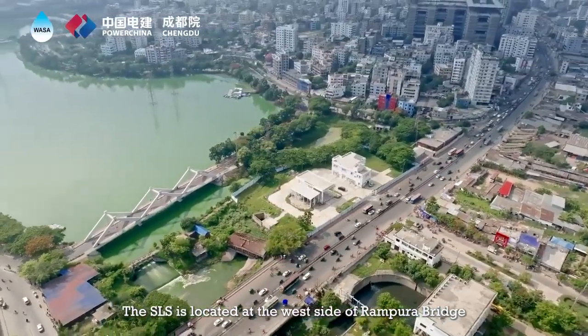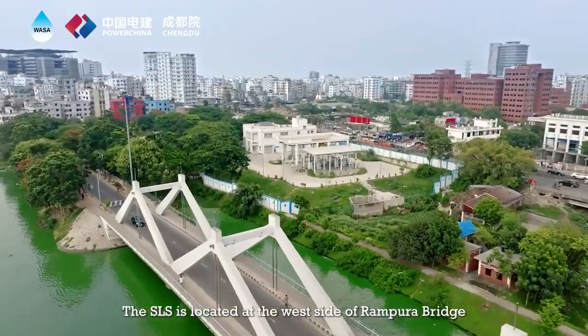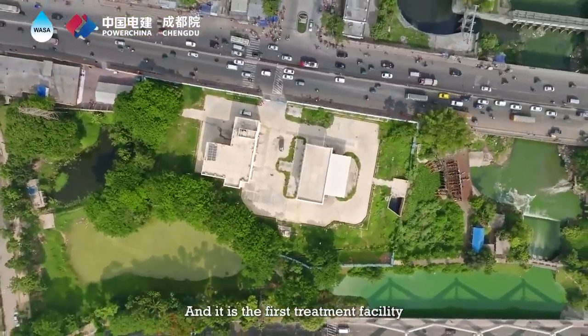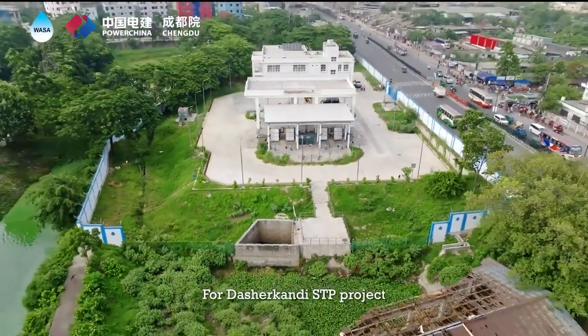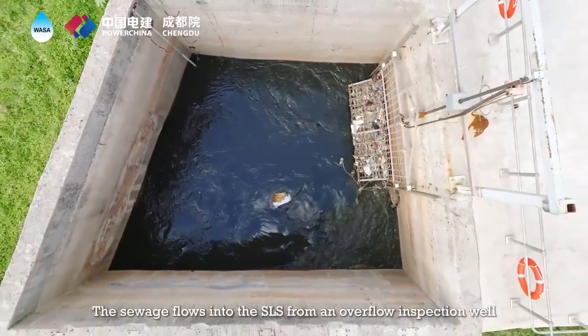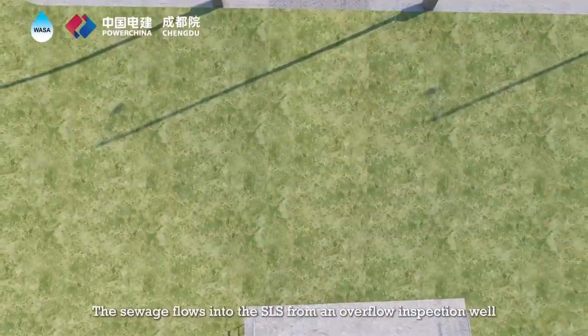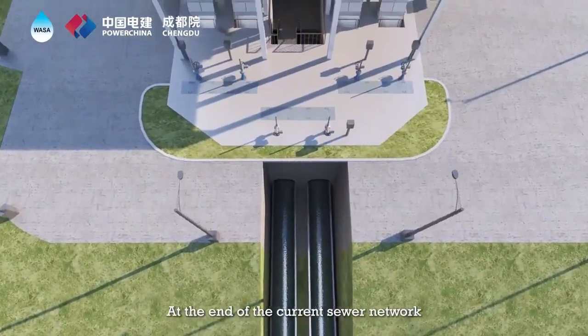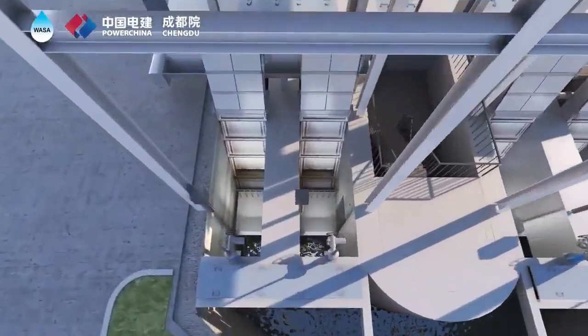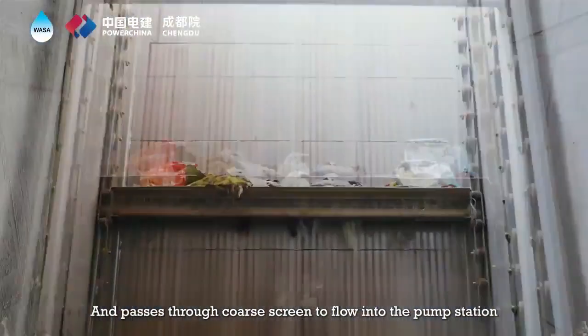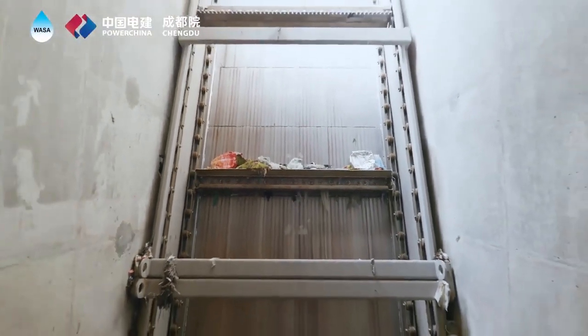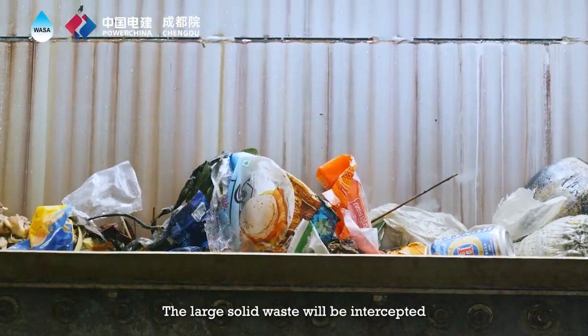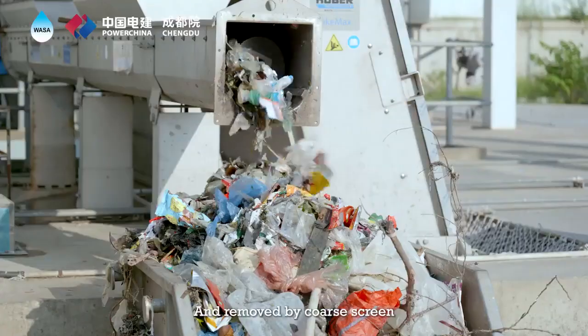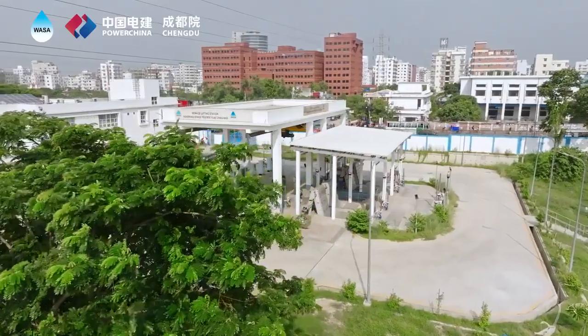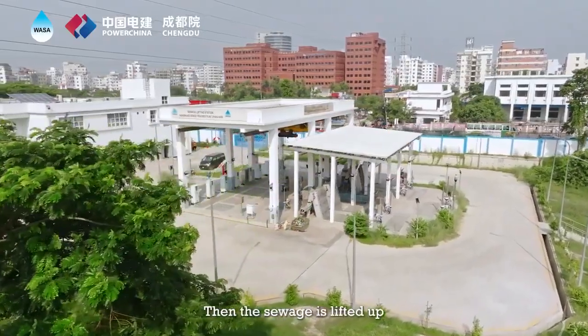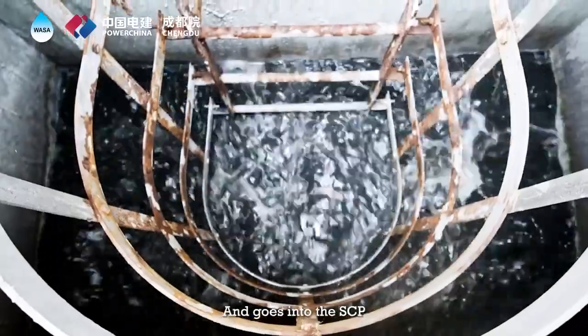The SLS is located at the west side of Rampura Bridge, and it is the first treatment facility for Dasherkandi STP project. The sewage flows into the SLS from an overflow inspection well at the end of the current sewer network and passes through coarse screen to flow into the pump station. The large solid waste will be intercepted and removed by coarse screen. Then the sewage is lifted up by sewage submersible pump and goes into the SCP.